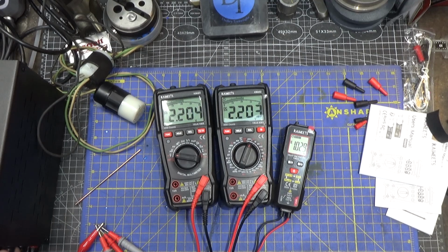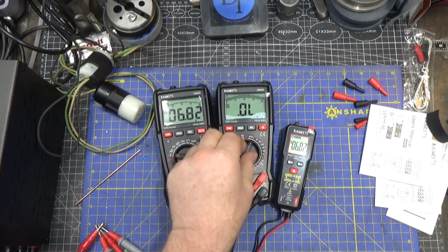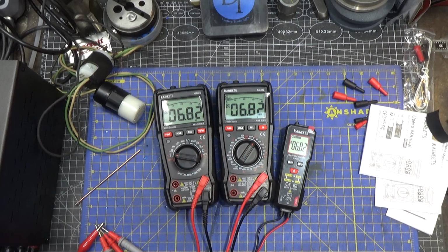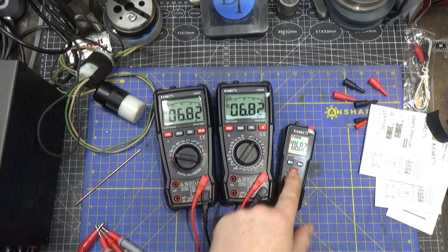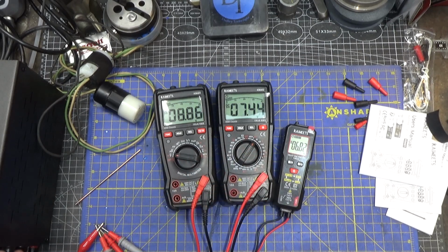Let's go up a little bit here. I'm over voltage on this one—at least you don't have a problem. You can flip up the scale: 6.82, 6.82, 6.82. Well, these are all calibrated to the same standard, it looks like. Look at that, that's pretty impressive.